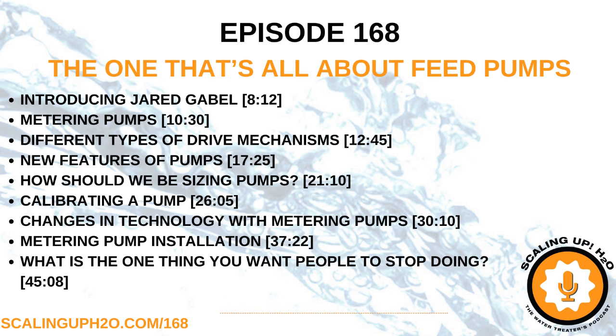That means do a draw down, not fill up into the calibration column. This ensures that the pump is actually moving chemistry and it's independent of the back pressure in the system. At that point, it's always pumping what is going through it on the suction side. So that's the best way to calibrate a pump.